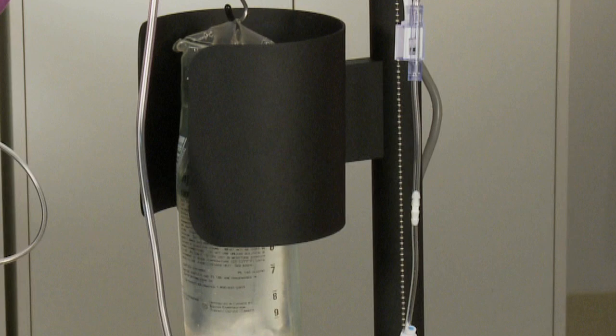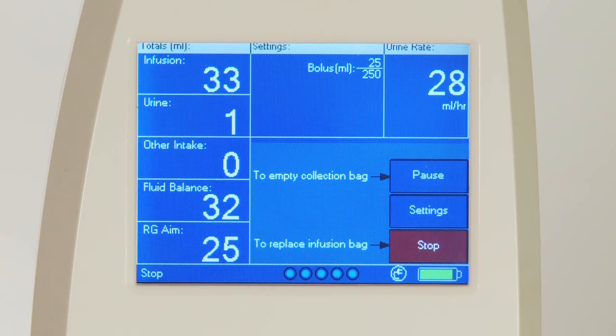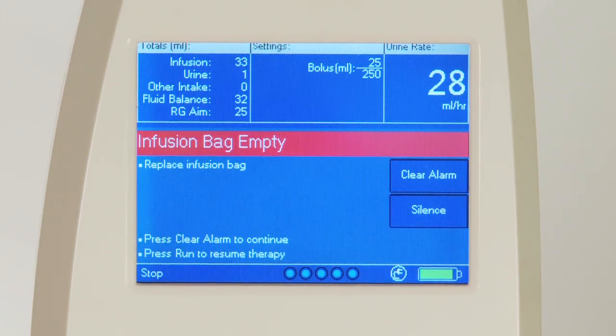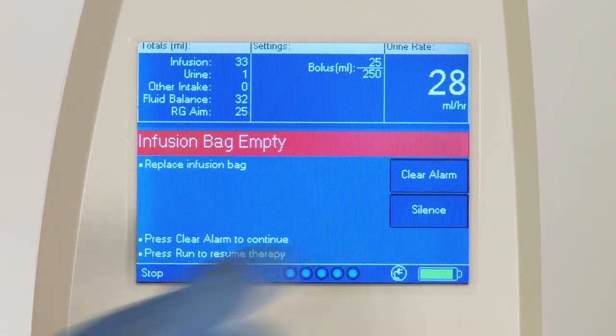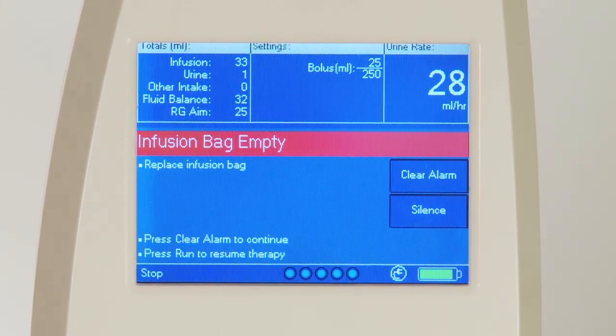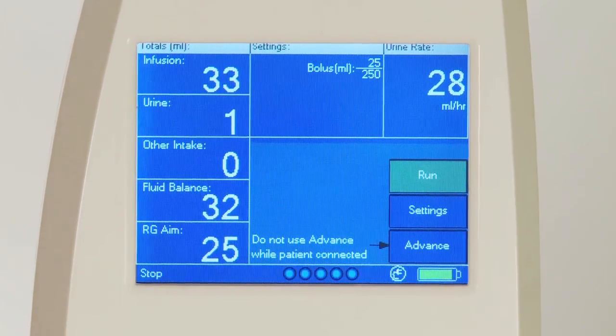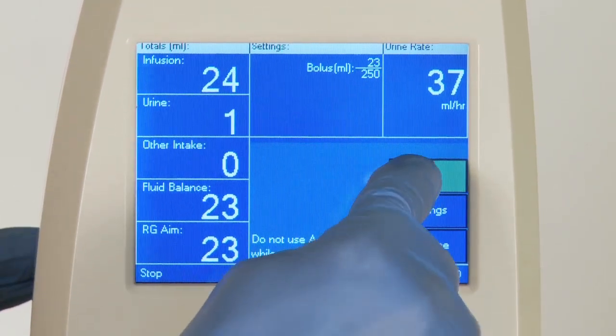The infusion bag should only be replaced during stop mode. If the infusion bag empty alert sounds, the alarm can be silenced by pressing the silence button. Press the clear alarm button to clear the alarm display. Replace the infusion bag and press Run to resume therapy.